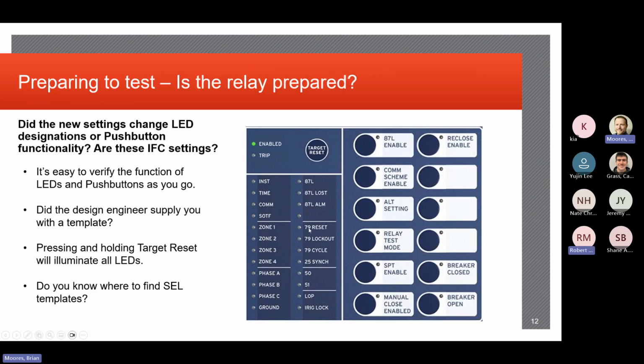So here's a front panel. Go ahead. I was curious, if you have relays communicating with each other within perhaps the same zone, and this might sound stupid, but if one sees the other one tripped off, can your SER collect the data that's occurring at that relay that wasn't affected but might have a transient in the system? Like if they're communicating with one another and it sees, oh, this one tripped off, or sends an output to trip. I guess just so you can monitor what happens throughout the whole system.